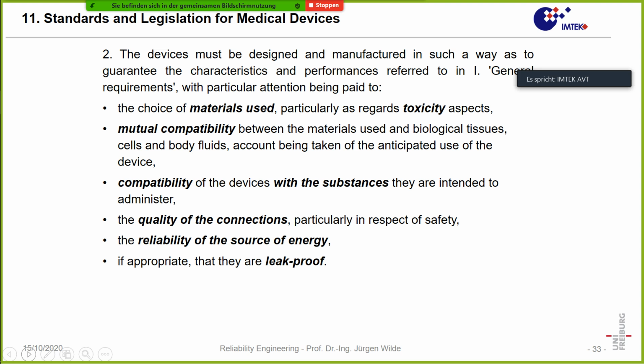So the cosmetic industry implants lots of silicones, but on the other hand also implantable electric devices often contain silicones because silicone is compatible with the body. And that's important, mutual compatibility between the materials and the biological tissue. That means two things. One is the material must not be toxic or in other way have a disadvantage for the bodies. That also can be if the material is too hard and has too sharp edges, that could lead to some reaction of the body.